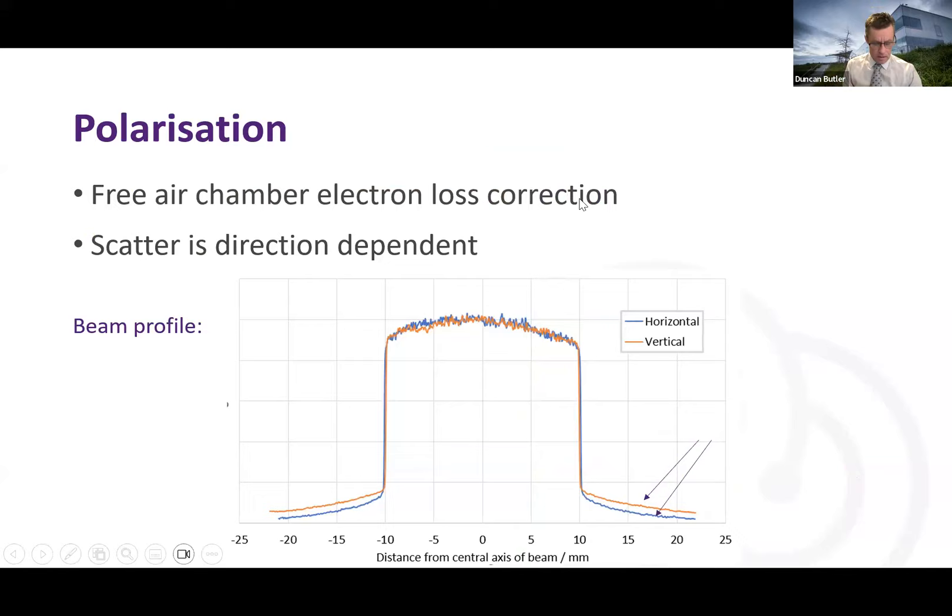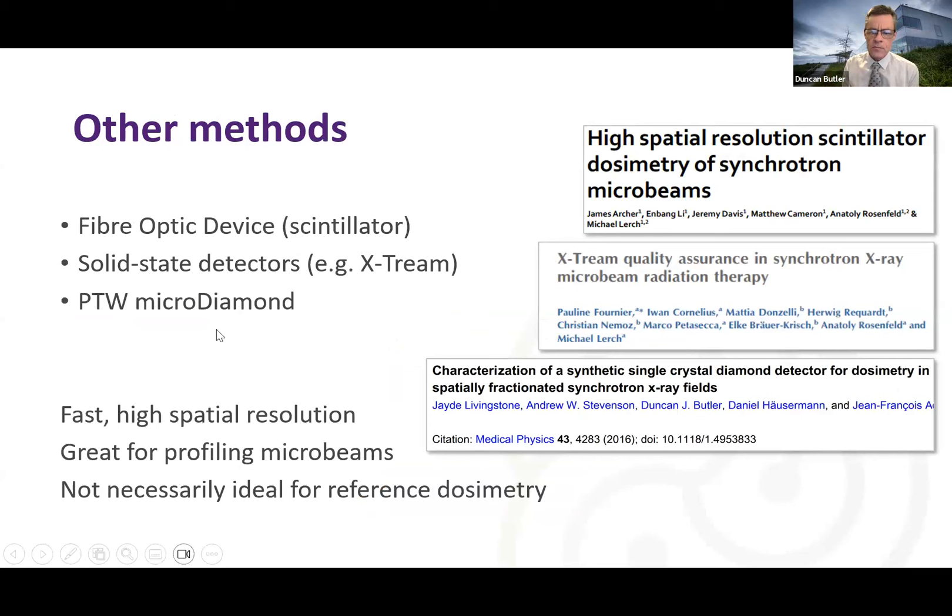And this plot shows something that took me a while to get my head around. Because the beam is polarized, it propagates through water a bit differently than if it wasn't polarized. In the field there's no difference, but the scattered radiation does show a slight difference, horizontal versus vertical, which you can see in this plot here. One of them is higher than the other. And as I said before, that's quite hard to model because many codes assume random polarization.